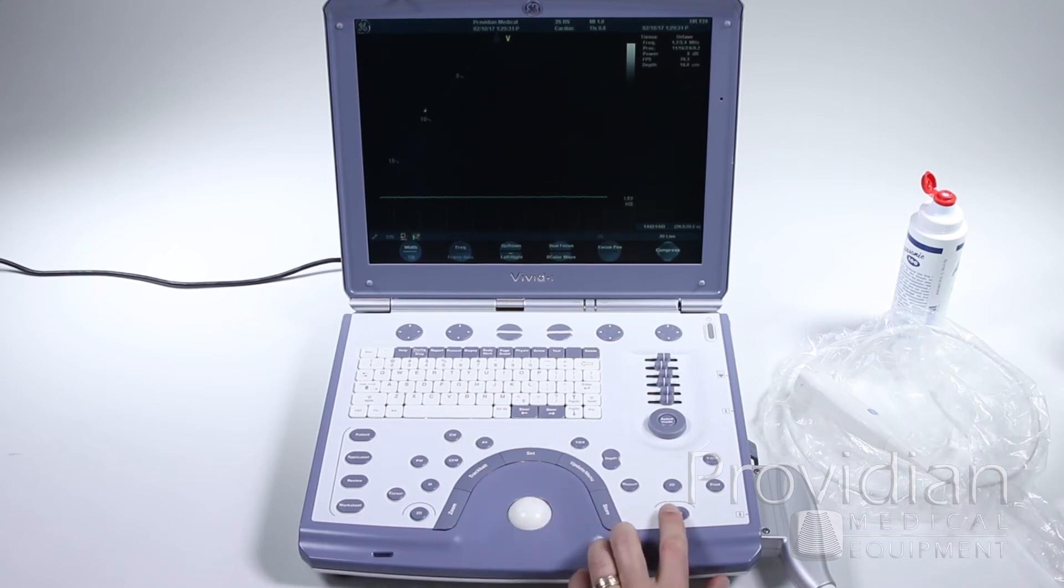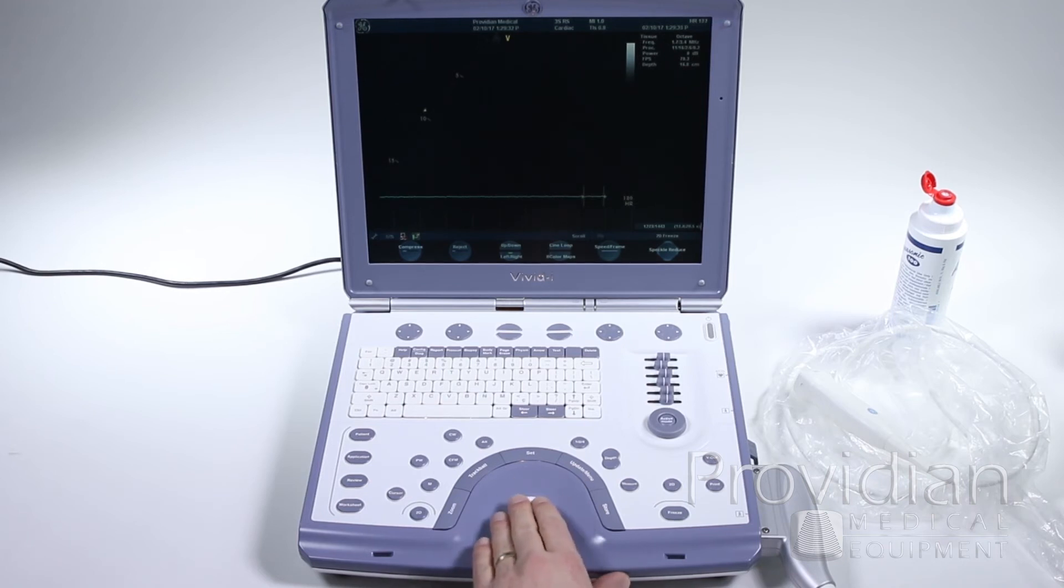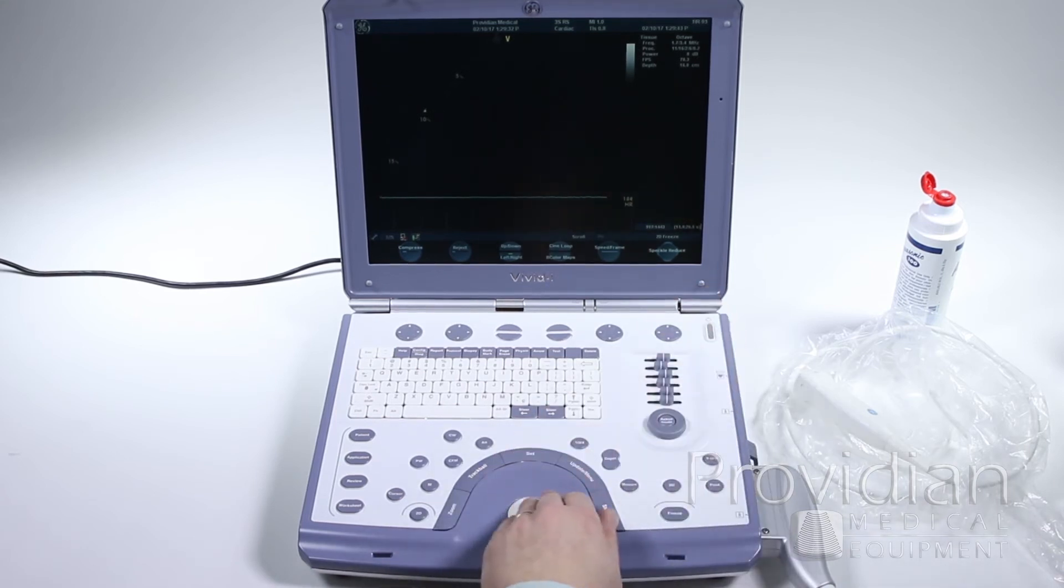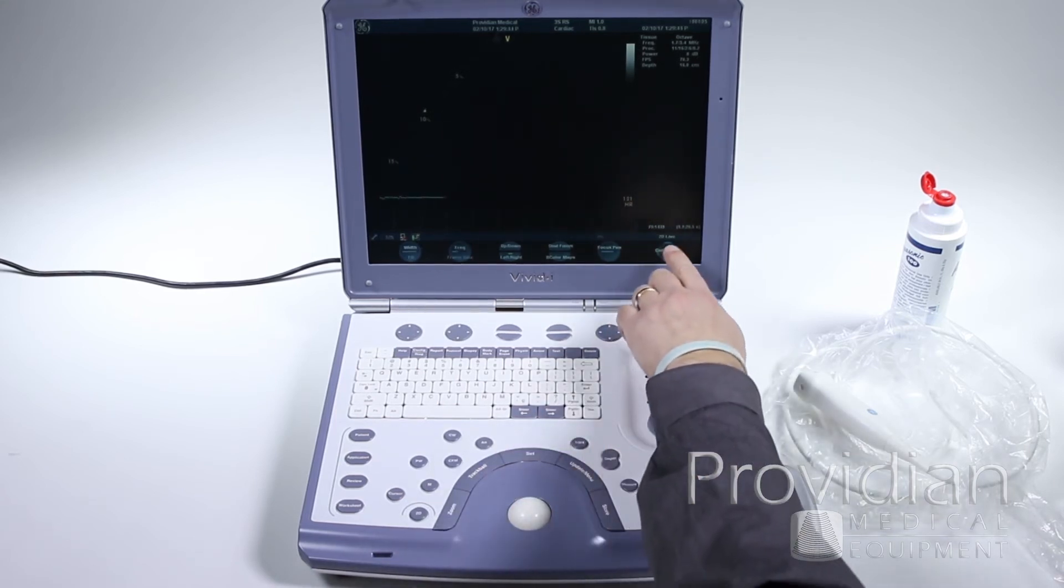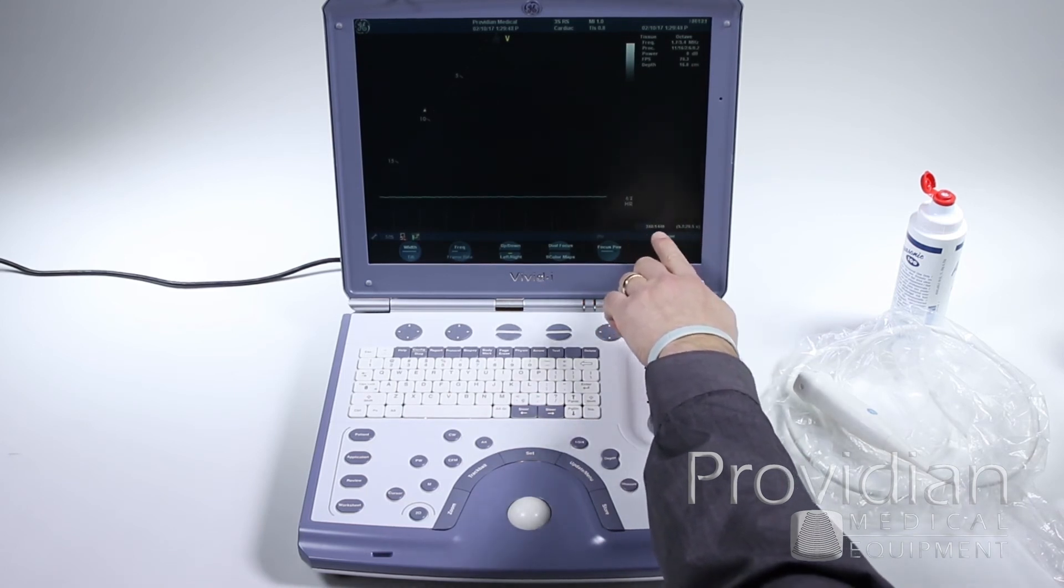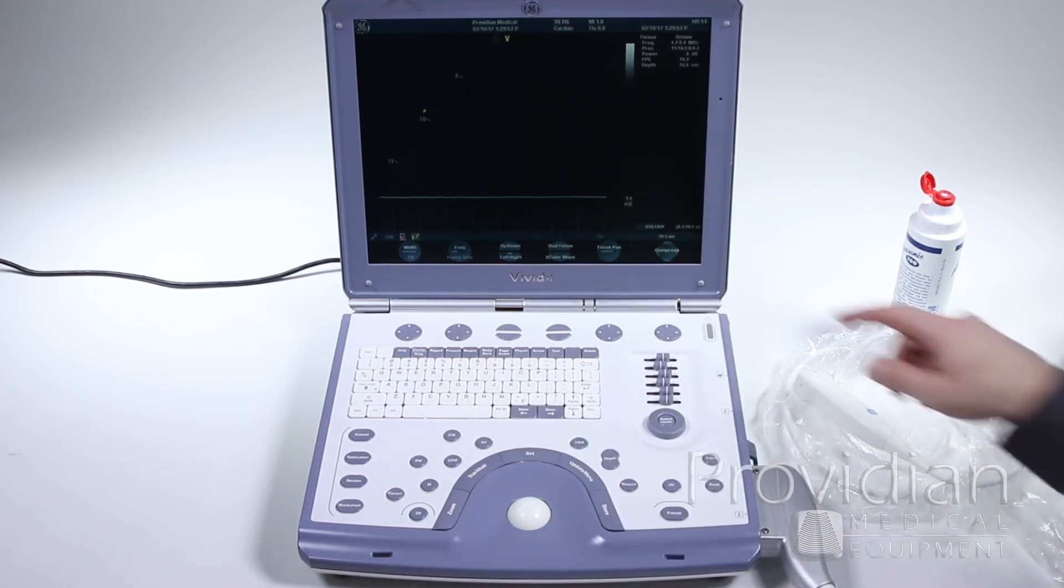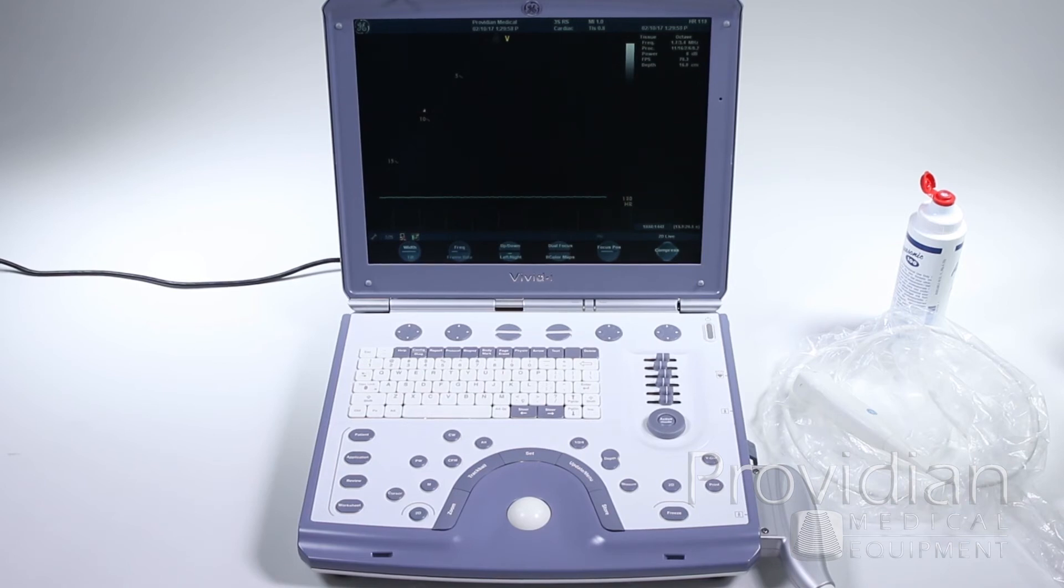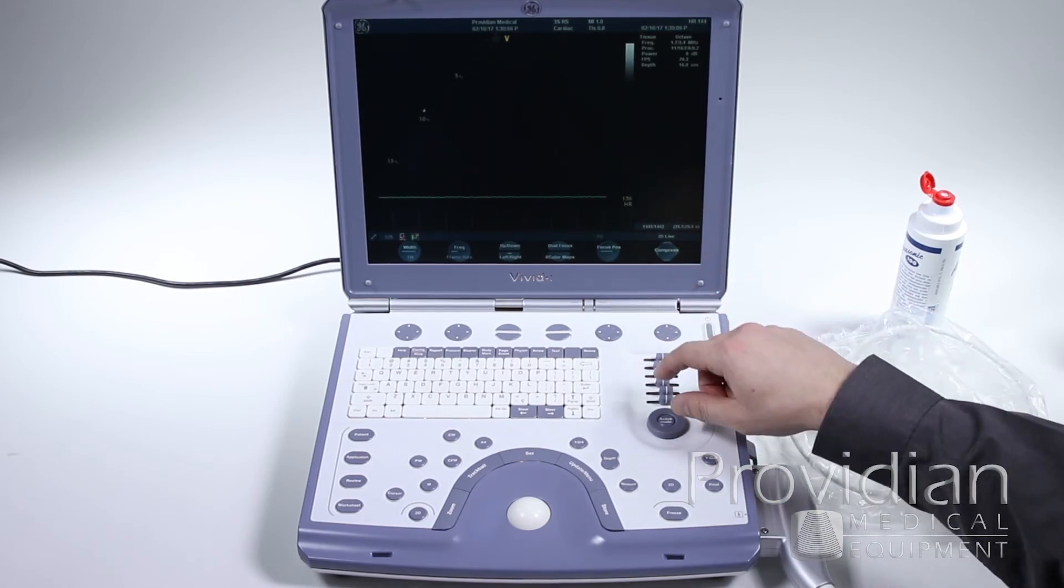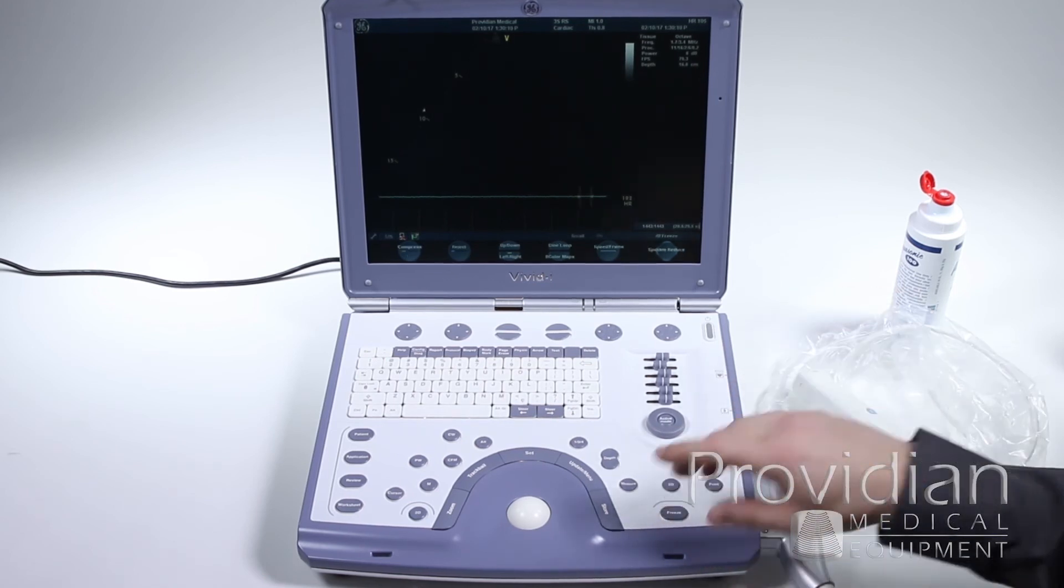For cine review, just click freeze and you automatically have your cine loop. We discussed this before about how many frames it has and the amount of time that is in the loop. If I unfreeze right now, it's telling me how many seconds I have in the loop. This is the buffer filling across right here. We're at 70 frames per second until this buffer fills up, which before it was about 20 seconds. That's when it will start erasing the beginning. So in general, if we're looking down here, it'll tell me about how many seconds I have to go back into the cine review. If I want to go back, I can just hit freeze.